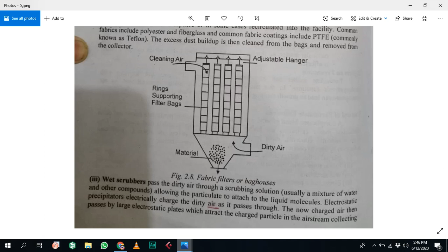Sometimes an electric field is applied on the whole of the dirty air, and the electrostatic precipitator electrically charges the dirty air as it passes through. The now charged air is then passed by the large electrostatic plates. When the air particles are charged, they travel toward the oppositely charged plates, so the particulate matter deposits on them, and we can easily remove it. The plates attract the large charged particles in the air stream, collecting them and leaving the clean air to the exhaust, or it may be recirculated.